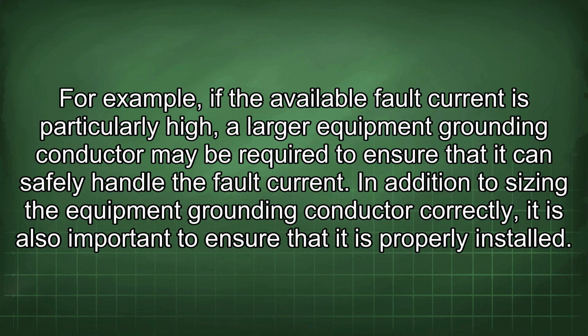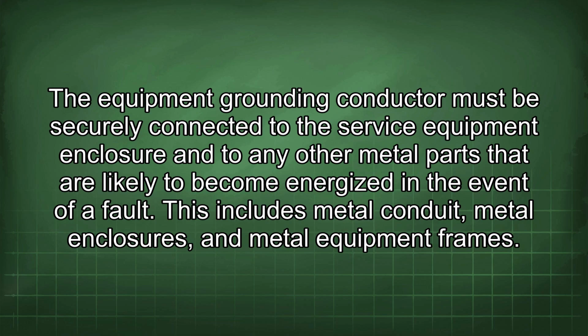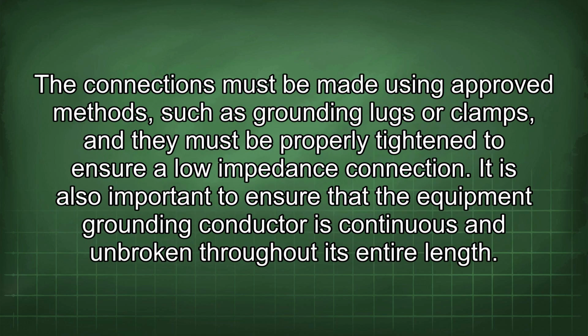In addition to sizing the equipment grounding conductor correctly, it is also important to ensure that it is properly installed. The equipment grounding conductor must be securely connected to the service equipment enclosure and to any other metal parts that are likely to become energized in the event of a fault. This includes metal conduit, metal enclosures, and metal equipment frames. The connections must be made using approved methods, such as grounding lugs or clamps, and they must be properly tightened to ensure a low impedance connection.